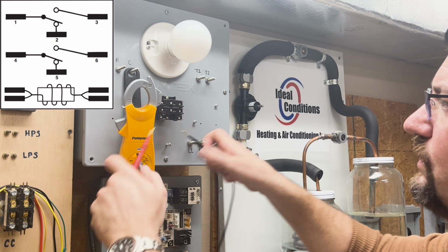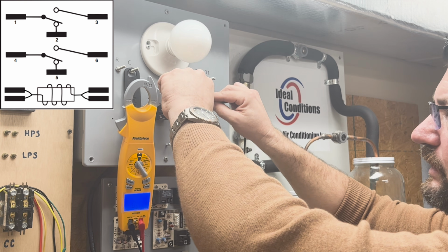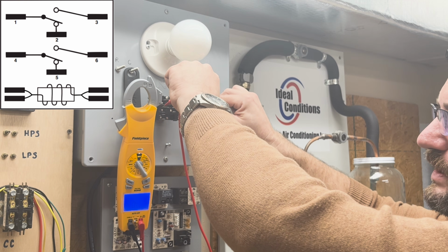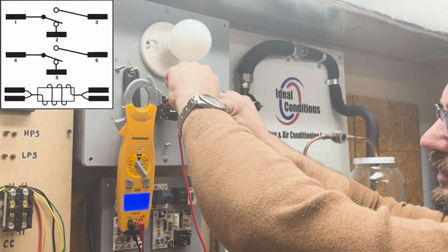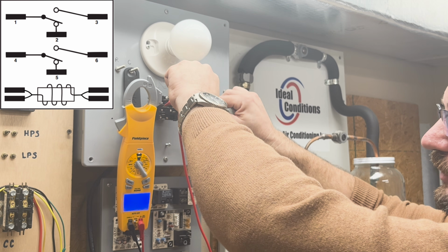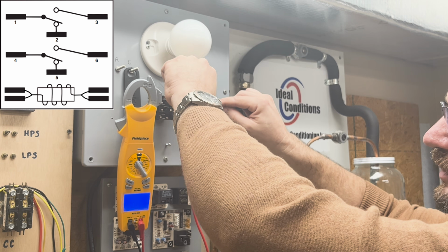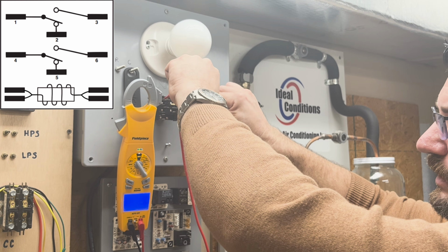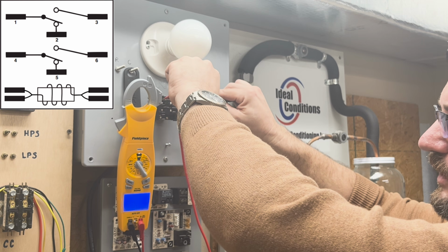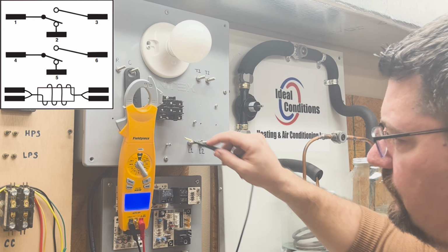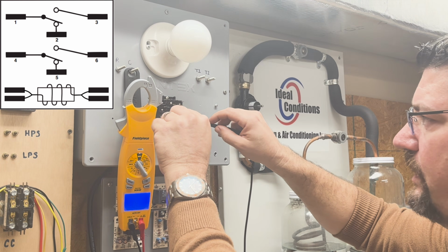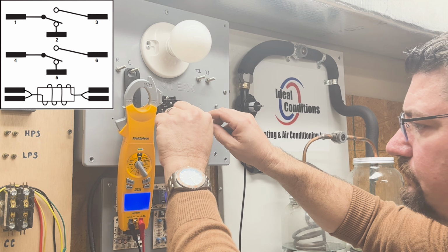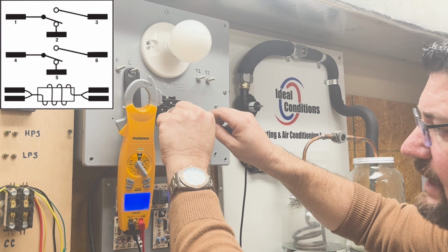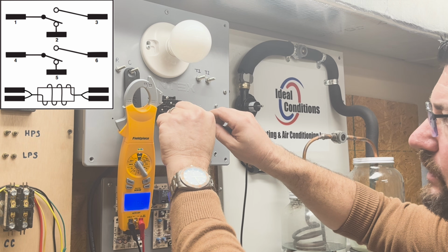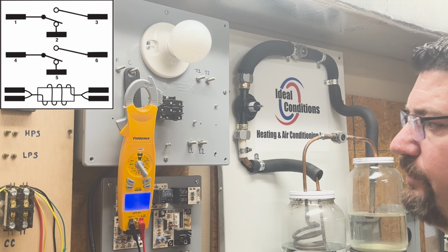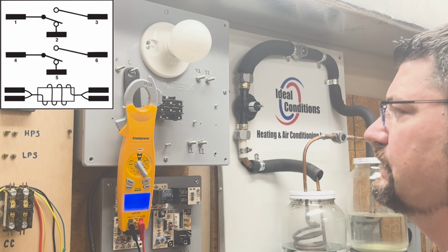Let me put that back on. I'm going to go 4 to 6. I read nothing because it's open. So I know 4 and 5 are closed. 4 and 6 are open. Same pole. 1 and 2 are closed. There's no resistance there. 1 and 3 are open. And if I wanted to go and read across my coil, I'll get a ringtone. And I'm going to get resistance there. I'm showing 19.3, 19.4. And that's a difference there of reading resistance and not reading resistance.